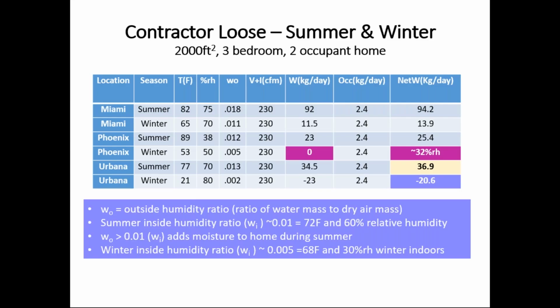So looking at Contractor Loose, with Miami having an average summer humidity of 0.018 and a winter of 0.011, we see that while winter does require some dehumidification, because that's so close to what we would like to maintain, the 0.01 inside the home humidity ratio, we don't have much dehumidification in the winter, but in the summer we've got a huge amount, almost 3 times what we have in Urbana, because of the extent and duration and overall high humidity level.